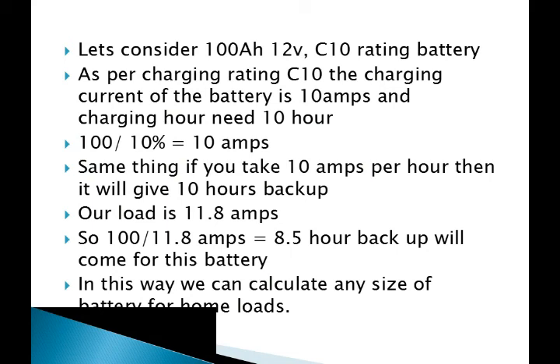Our required load current is 11.8 amperes, and our battery capacity is 100Ah. So we divide: 100 divided by 11.8 equals approximately 8.5 hours of backup. Since we only need 7 hours, this 100Ah battery will give us 8.5 hours of backup, which is sufficient.